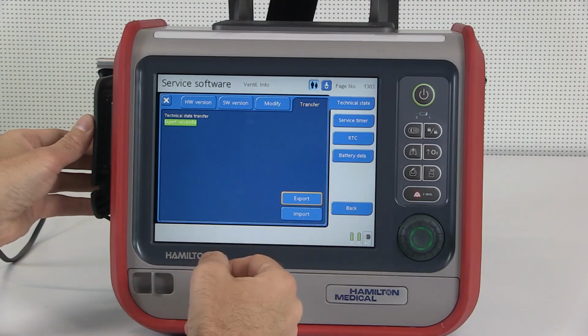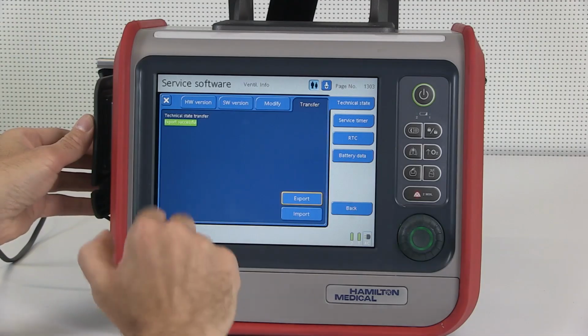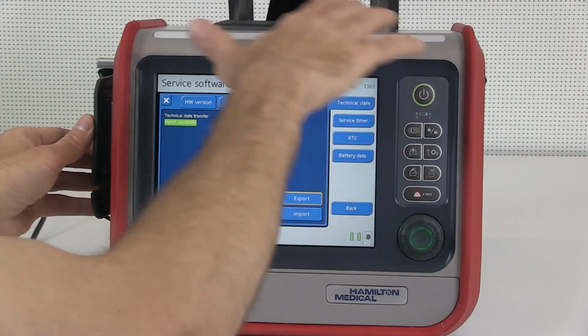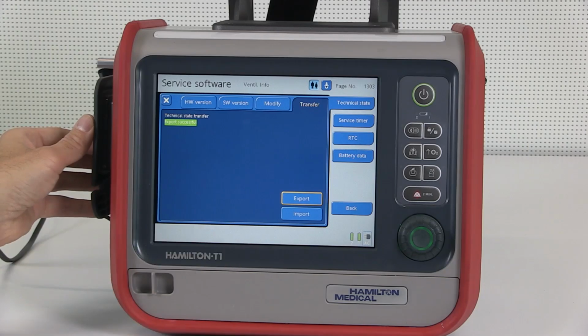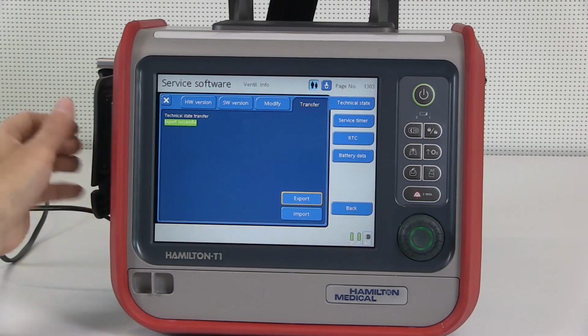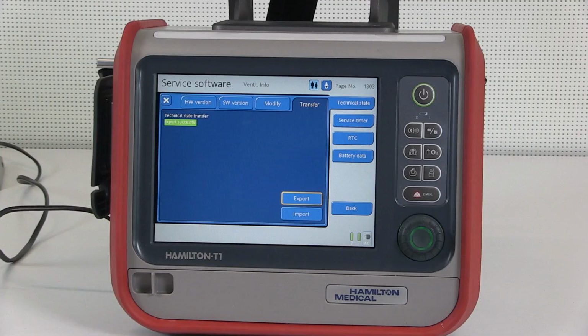Transfer gives you the possibility to export the technical state file onto a USB flash drive. This file has a CSV file extension. It includes all serial numbers of the parts that are listed in the Modify tab. It is useful to have it in case the control board needs to be replaced. With the help of this file, it is possible to import all the part-specific numbers automatically once you have entered the device's serial number.